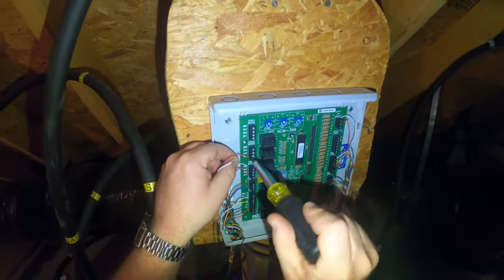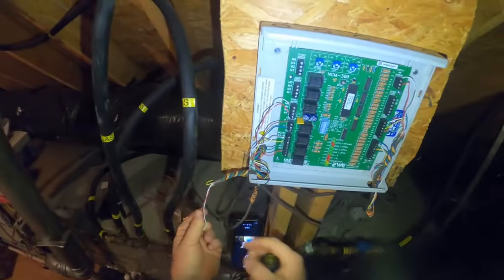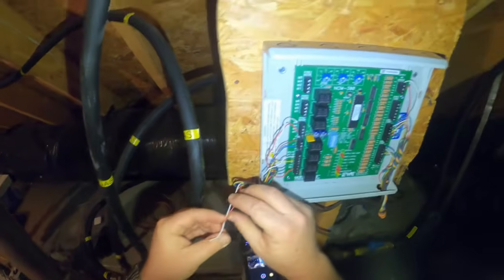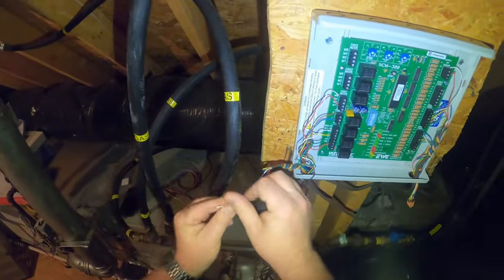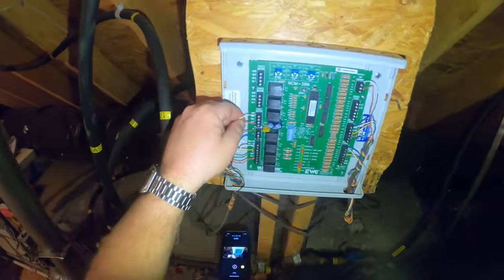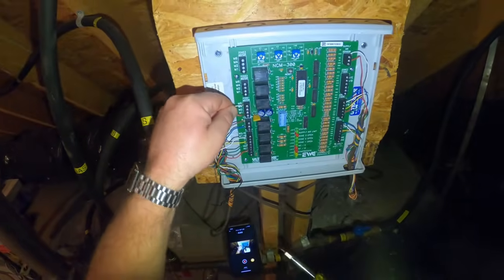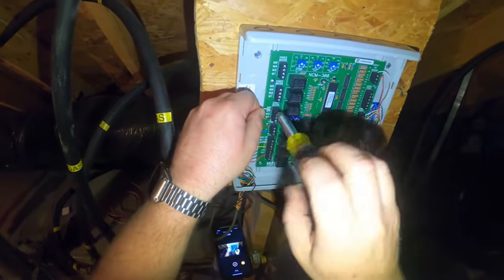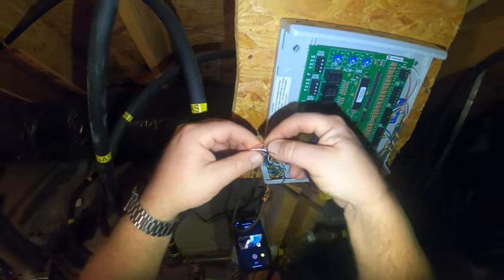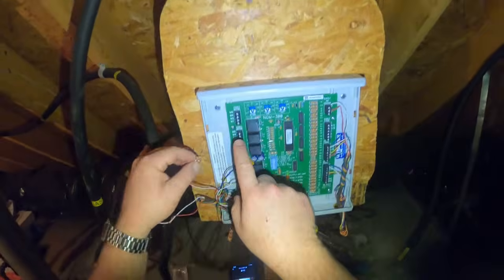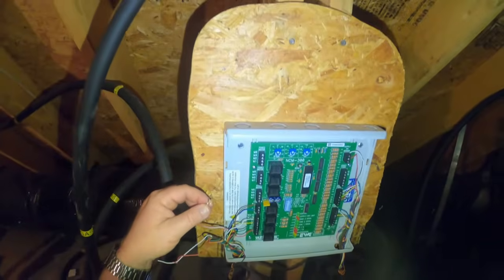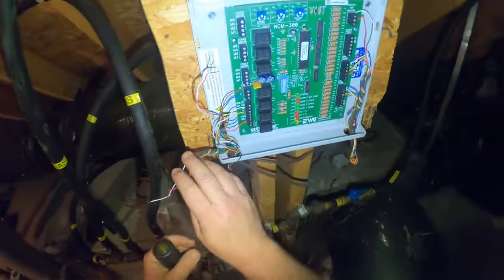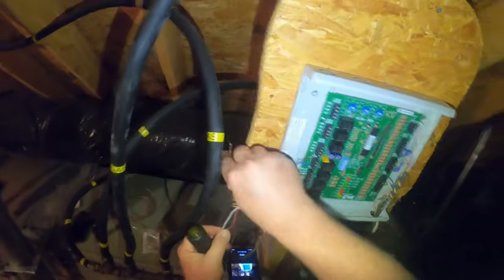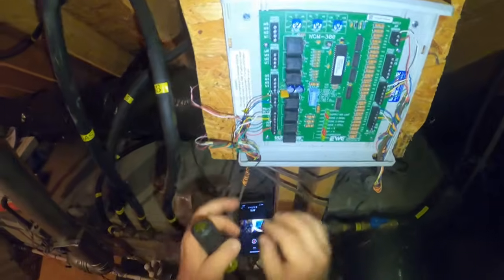So zone 2 here, I'm gonna have to assume that's gonna be our upstairs zone, because they are not using different colors, which is what I would typically do. That way I know which ones. You got red and white going to both your zone damper motors over there. So I mean, I can check continuity on them and figure out which one goes where. But we're gonna say this one is hooked up to here, this one's hooked up to there. So I'm gonna have zone 1 and zone 2. And we'll put those over to the side.